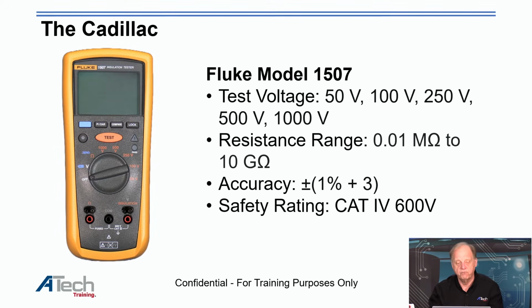We're going to look at some meters and the process you might want to think about when searching for meters for your shop. The first meter has test voltages of 50, 100, 250, 500, and 1,000 volts. The resistance range is 0.01 megohms to 10 gigaohms, a great big range for testing. The accuracy is plus or minus 1% plus 3, which is interesting how they express that. The safety rating is Cat 4, 600 volts. That meter's doing its job.